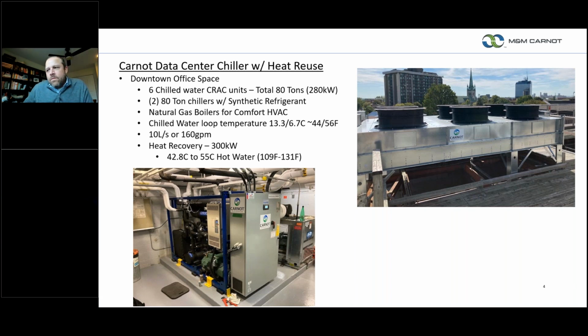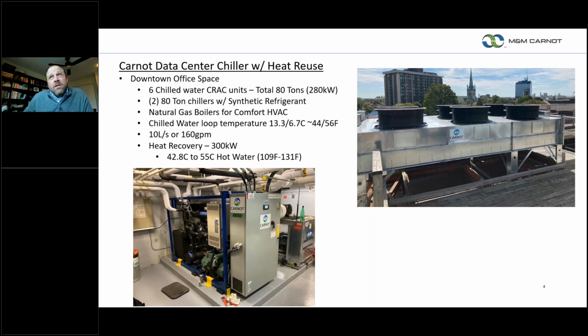So that building was heated by natural gas boilers, and I think there were 3 in the building, but we figured out a way to take the 80-ton machine that would handle the load for the data center space and basically provide 300 kW worth of heat that the building could use. So we were eliminating the use of the natural gas boiler, but running a chiller that would move the heat from the data center into the building space.